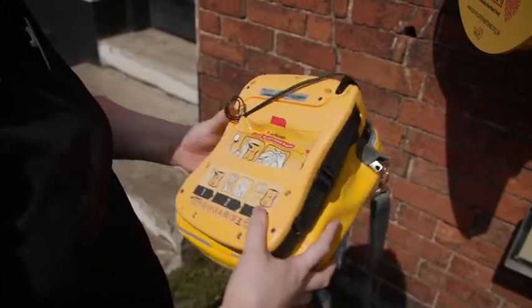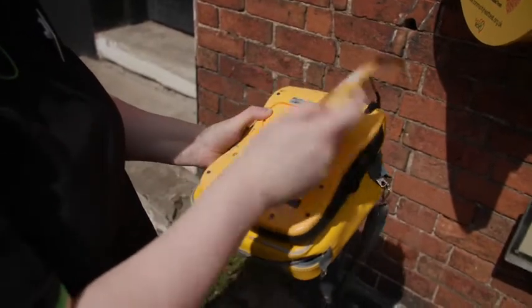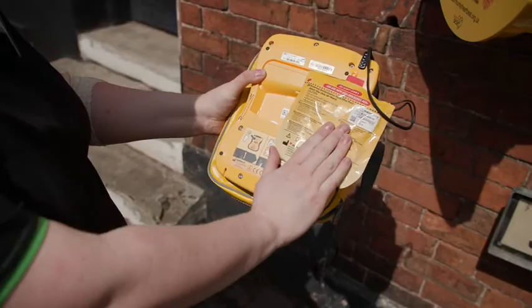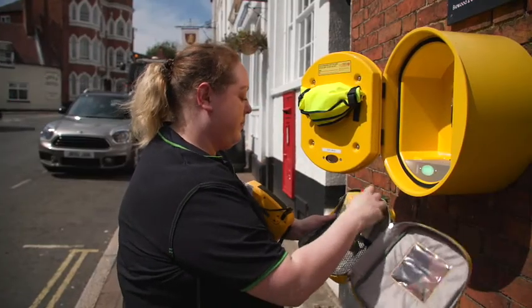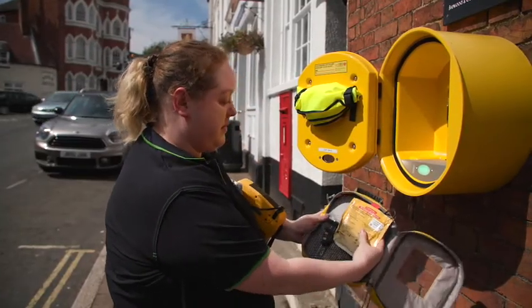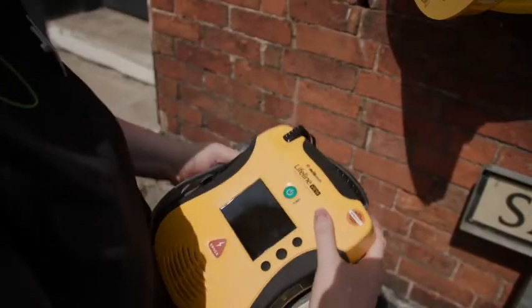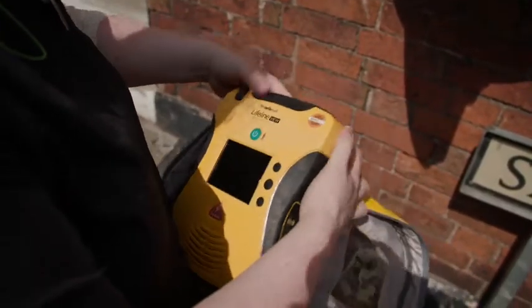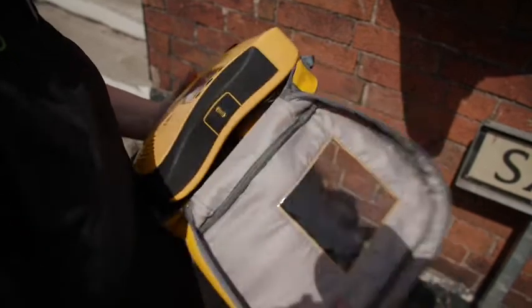Look at the dates on the electrodes. Are they in date? If there are spare electrodes present, are these also in date? And, of course, is the green indicator light on the defibrillator flashing? If it is not, and is showing red, then there is a problem, and we would need to investigate further.